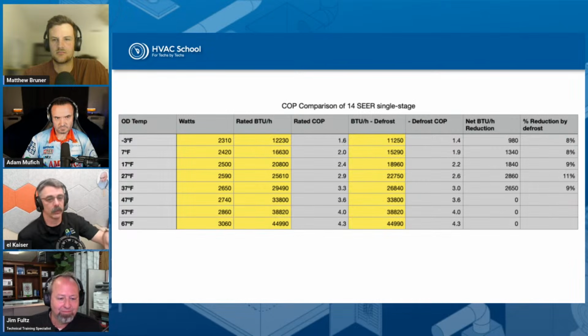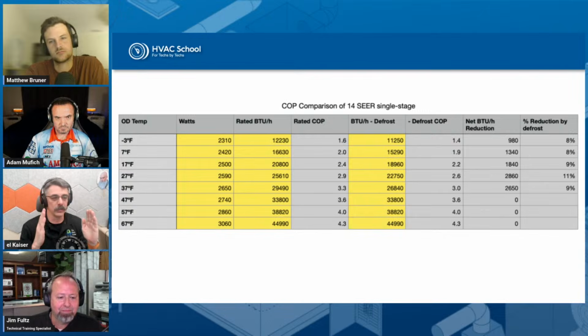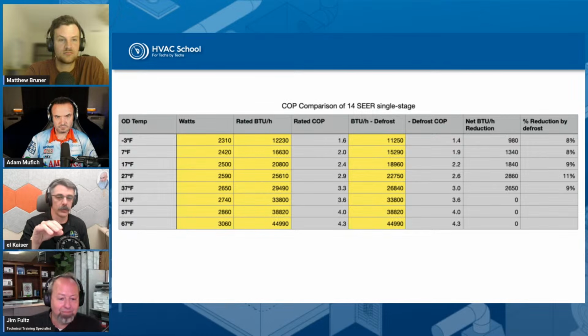So just real quick on this one, I pulled a 14 SEER single stage, and the particular manufacturer I got the data from showed the rated BTUs, and then the BTUs minus the defrost cycle. I wanted to show the difference in COP there. So if you look across the left, it shows the wattage, the rated BTUs, the rated COP, then the BTUs minus the defrost and the minus-defrost COP next to that. Then I'm showing the net BTUs per hour reduction.